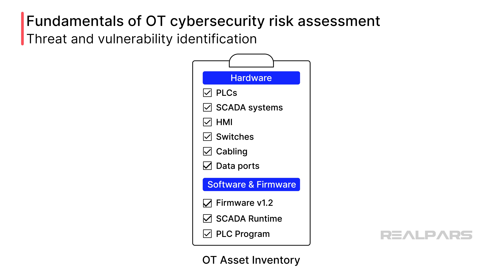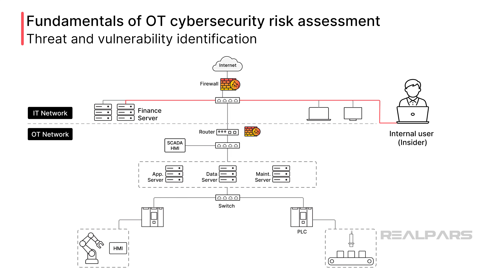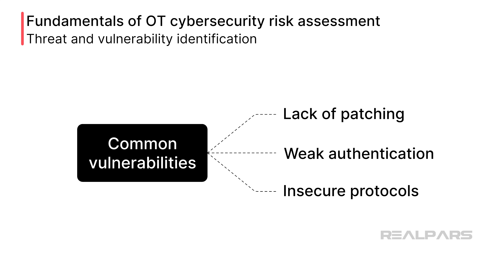Once we have all of our assets listed, we know all of the items that might be attacked. Next, we need to identify the types of threats our systems may invite. These threats can be internal, from insiders such as skimming funds from accounts or inadvertent misconfigurations of network switches that allow bypassing of user authentication requirements. Threats can also be external, from internet sources, malware, hackers, or nation-state actors after valuable assets such as formulations and recipes. Often forgotten are common vulnerabilities with legacy OT hardware and software, such as the lack of patching, weak authentication, and insecure protocols.